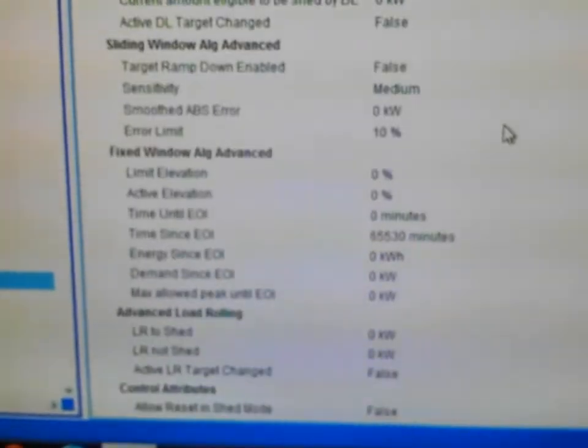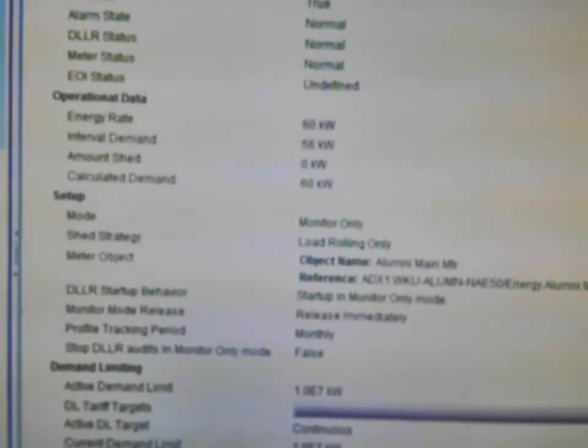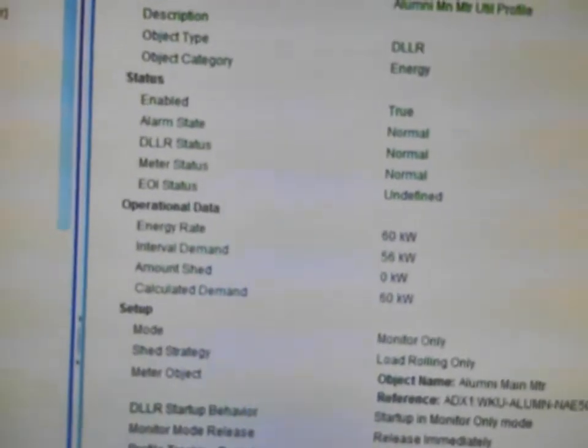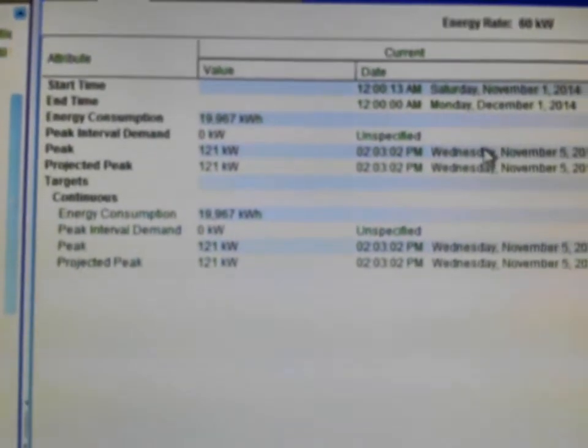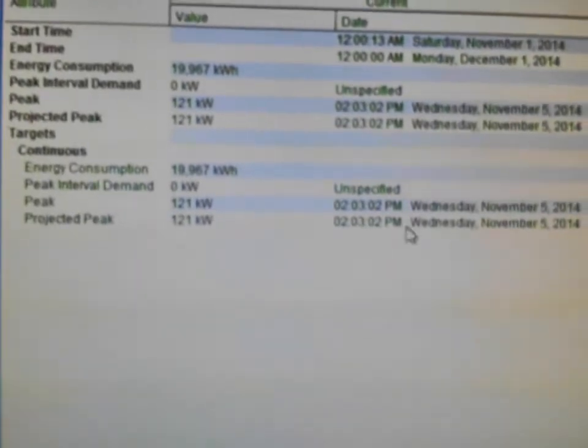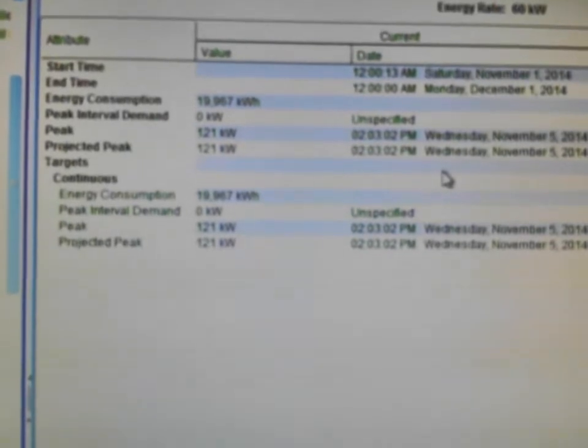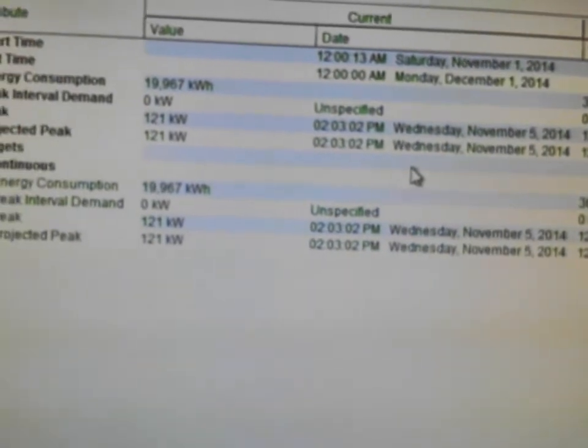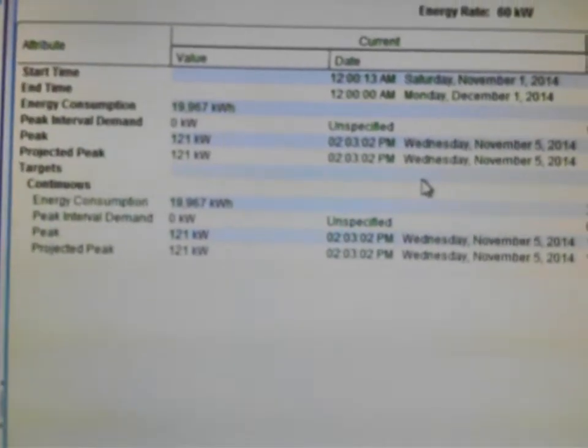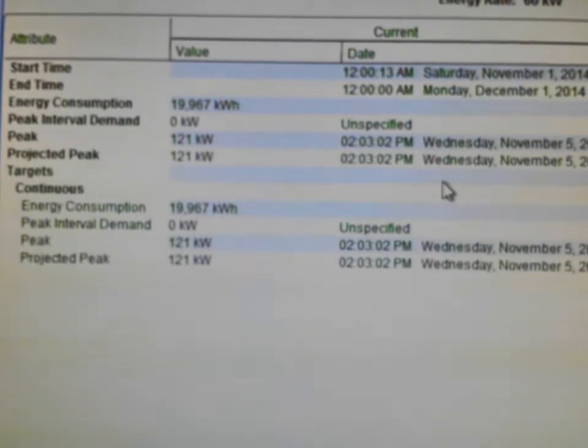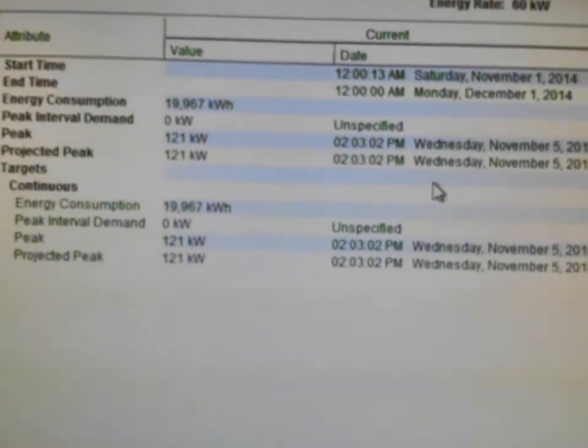One thing you need to be cautious of: if power is lost to the NAE or the NCE — whichever device you are using to store this information — this data can easily be lost. I recommend that you make regular printouts or transfer this information regularly to another device, such as an Excel spreadsheet, or print a hard copy. That way, if you lose power or have to reset an NAE, you will not lose all of your utility profile.